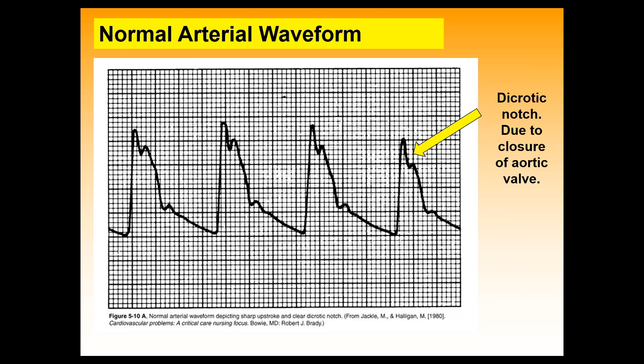And one of the ways in which you can test that, if you still have the transducers with the little pigtails on them, we'll see one in a bit here, is by pulling that little pigtail and letting it go. Only the clinicians should be doing it. It introduces a step or an impulse function into the system. So you get a pulse here, maybe 300 millimeters of mercury, a small little bolus of fluid, and you can measure, looking at the response, how the system responds to that impulse. And if you only get maybe one little oscillation in there, that's typically the hallmark of a good critically damped system.